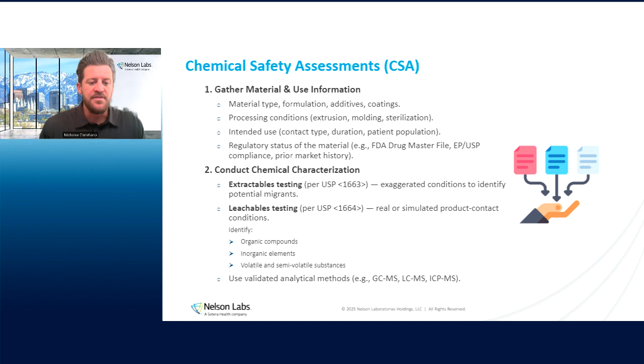And then step 2 would be conducting that chemical characterization testing. So we have our extractables or leachables testing, right, to understand potential migrants from our materials, and also our expected leachables under expected use cases, and potentially in simulated use cases as well, as we see in leachables testing. There we're identifying our organic compounds, or inorganics, or our heavy metals, as mentioned, and in doing so, our volatile and semi-volatile substances, typically. There we're using multiple analytical methods, as we normally would during those chemical characterization tests.